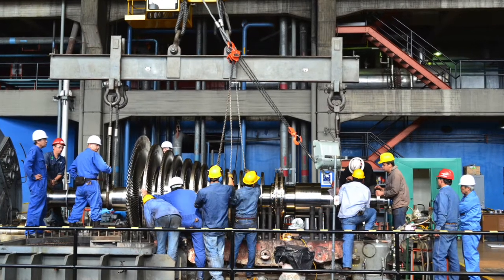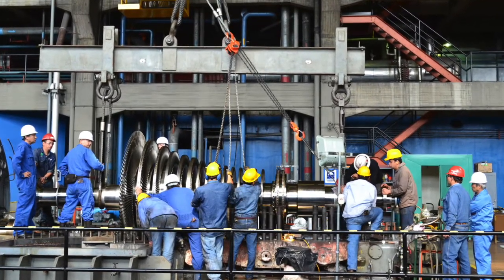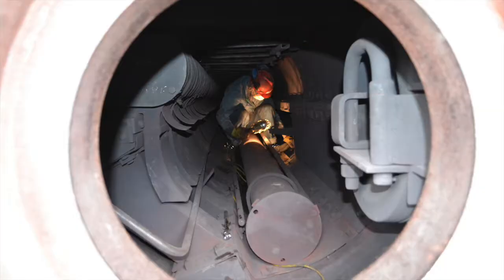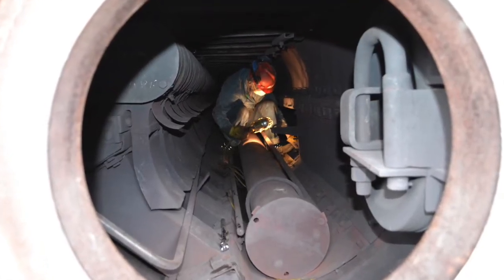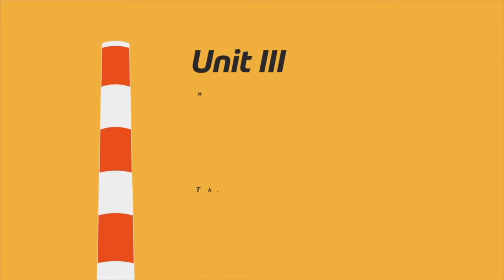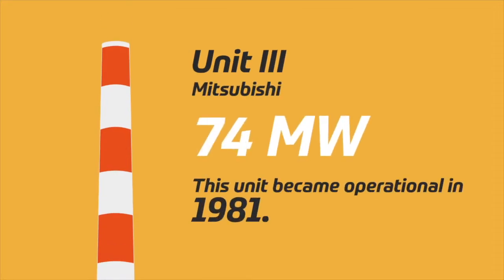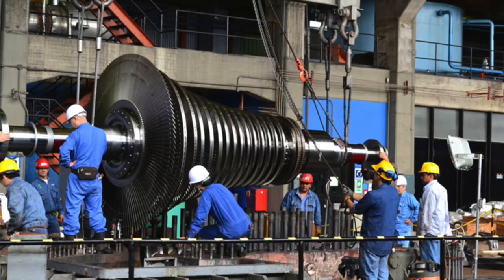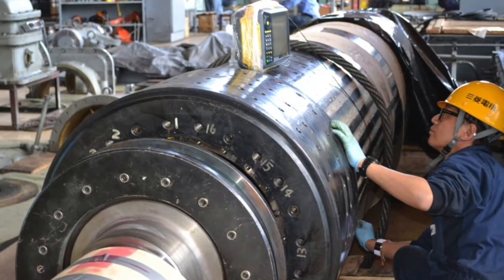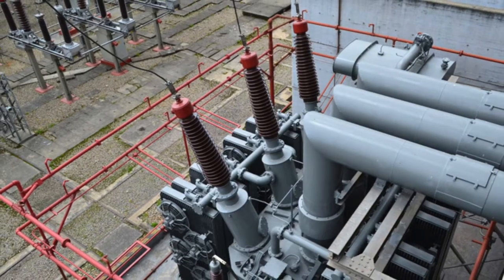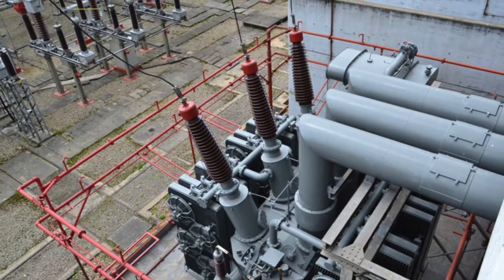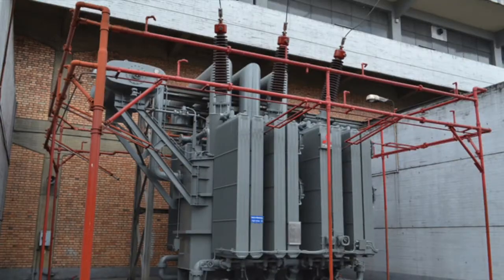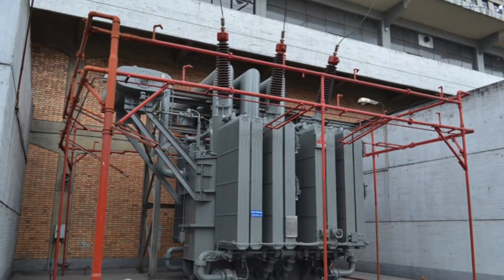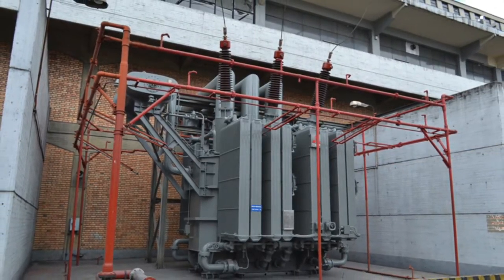Unit 3, also a Mitsubishi, has similar characteristics to Unit 2 and became operational in 1981 with a gross capacity of 74 megawatts. This unit is scheduled for retrofit in 2017. Total investments of around $6.5 million will grant GENSA an additional capacity of 4.36 megawatts per hour. Additionally, GENSA will buy a 90 MVA transformer to replace the current transformer and leave the current one as backup for Units 2 and 3, according to a past recommendation of the Loss Control Report.